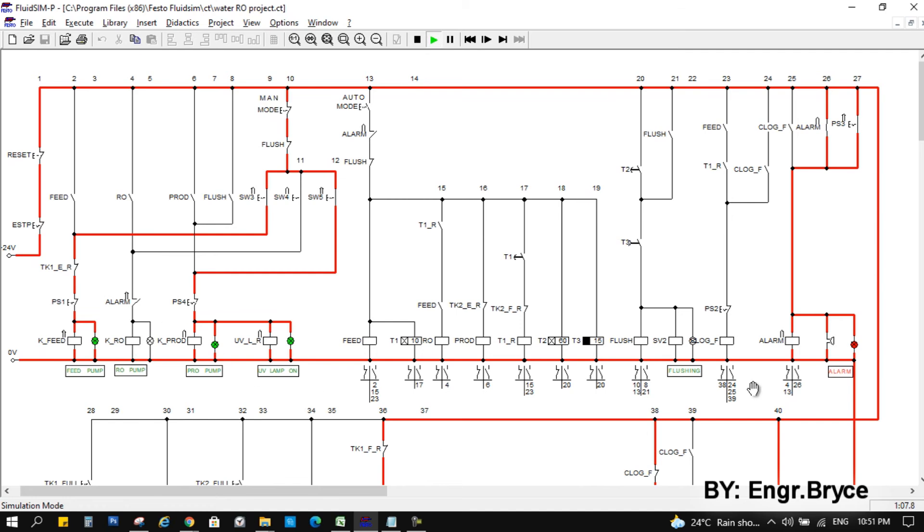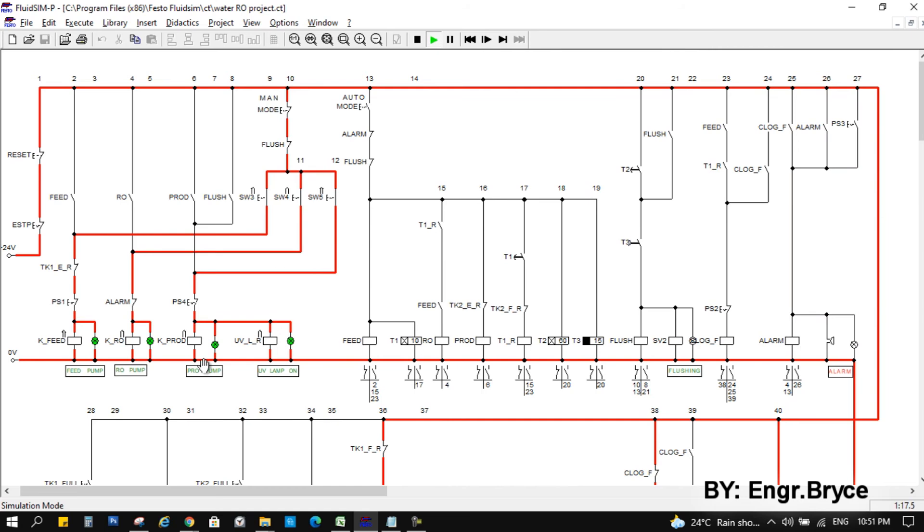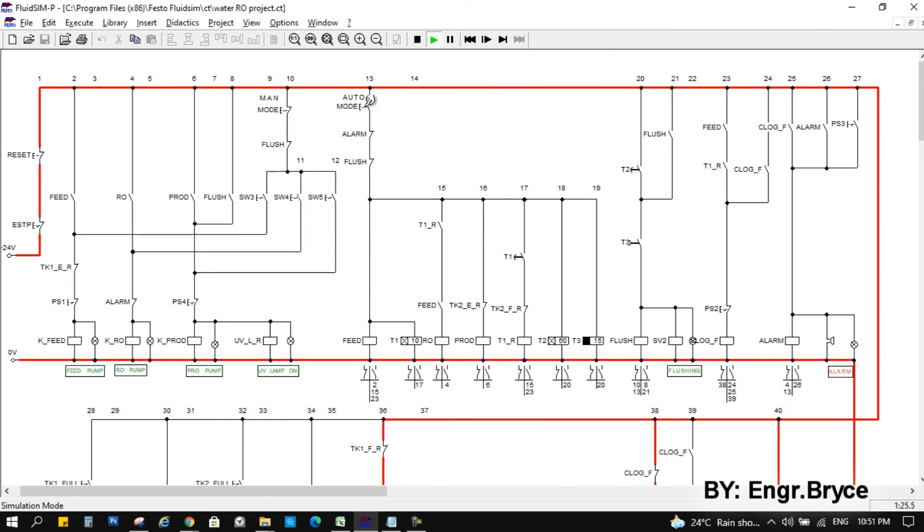We have here a pressure switch number three for the output of the RO pump for overpressure. So as you can see here, it triggered the alarm and turned off the RO pump. So yes, reset to reset the alarm. Okay, we will turn off now. And let's go to automatic mode.